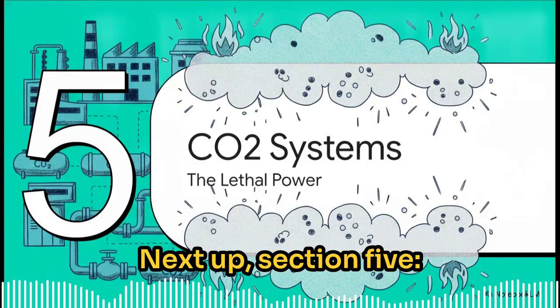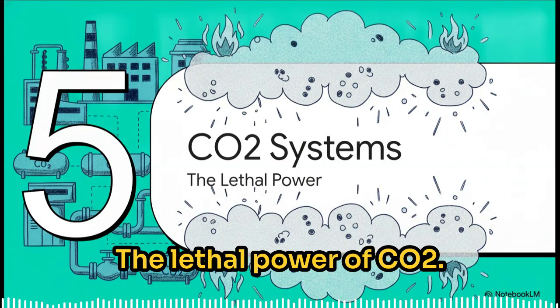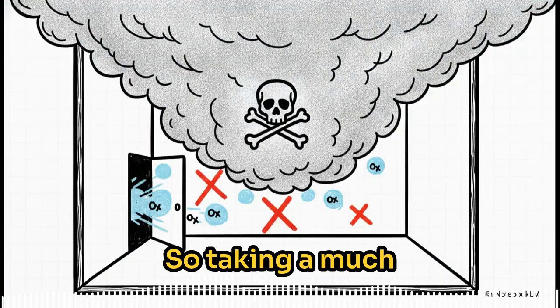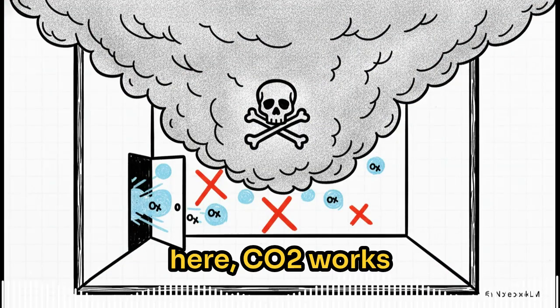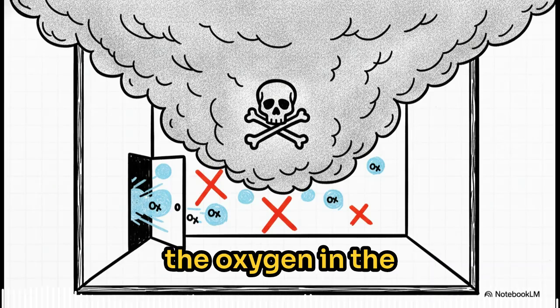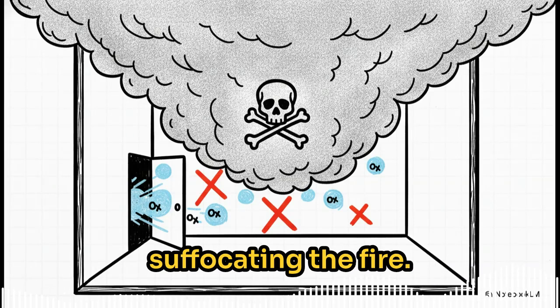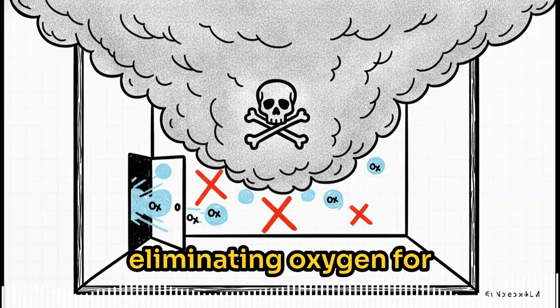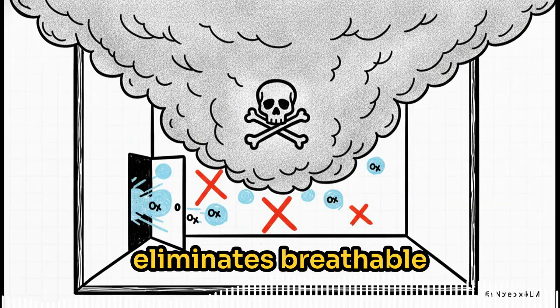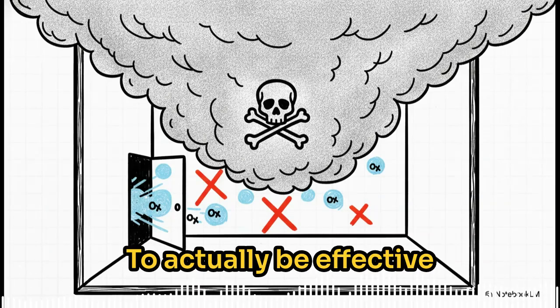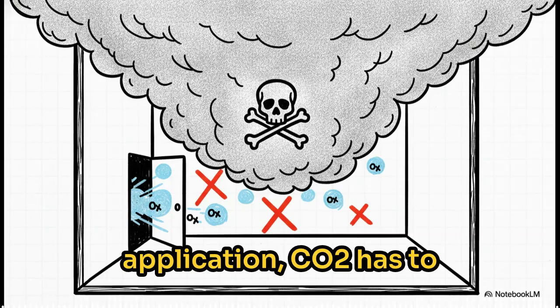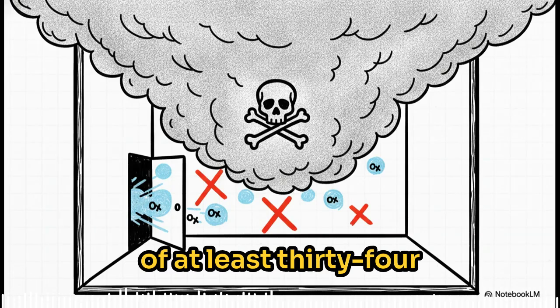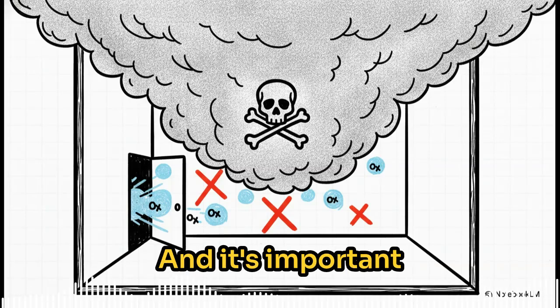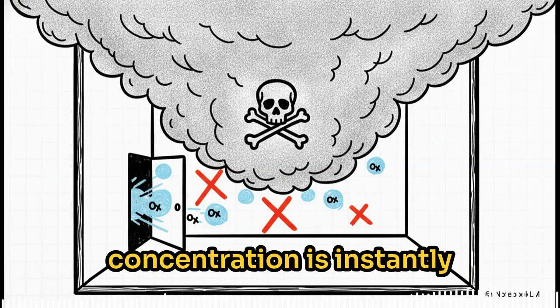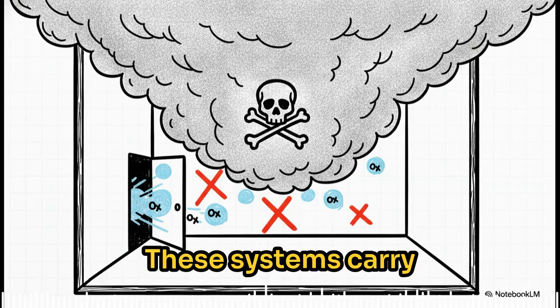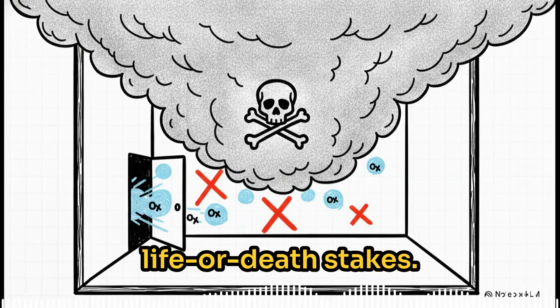Next, Section 5, the lethal power of CO2. Taking a more serious tone here, CO2 works primarily by displacing the oxygen in the environment, effectively suffocating the fire. But by eliminating oxygen for the fire, it completely eliminates breathable oxygen for humans. To be effective in a total flooding application, CO2 has to reach a concentration of at least 34% in the room, and that concentration is instantly lethal to human beings. These systems carry immense, absolute life-or-death stakes.